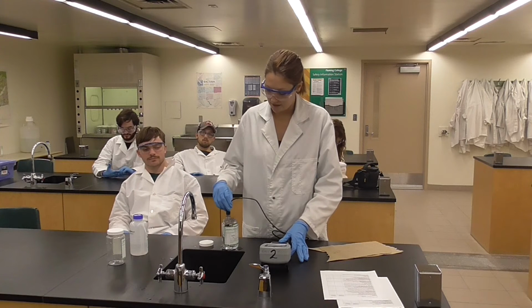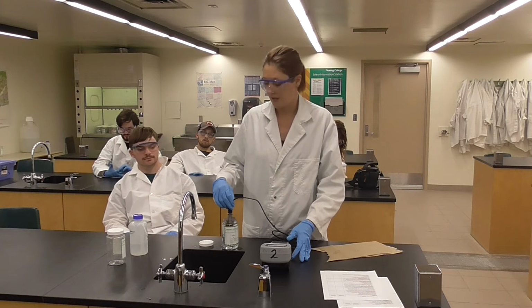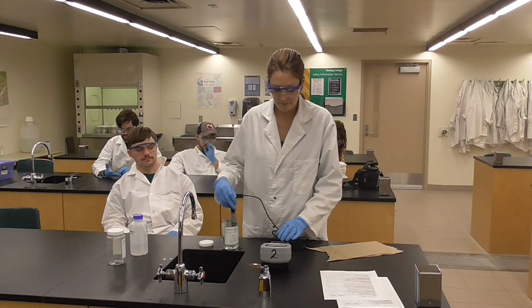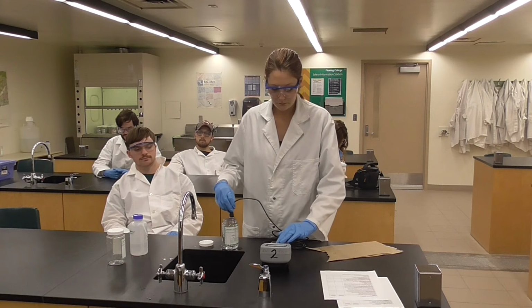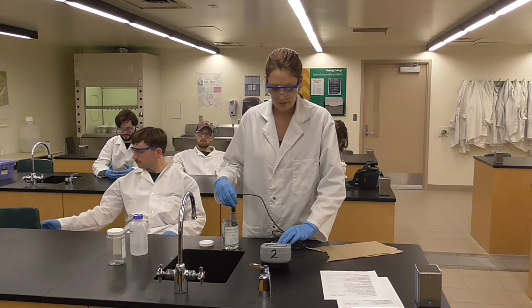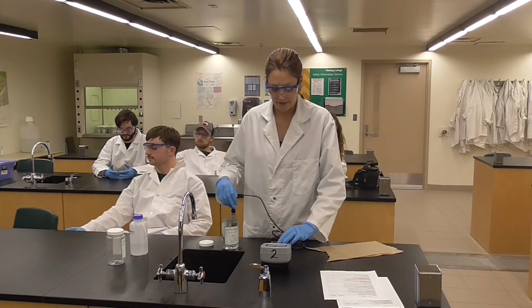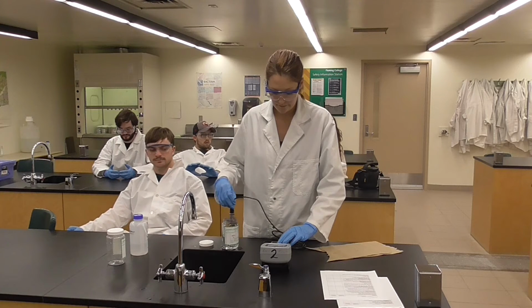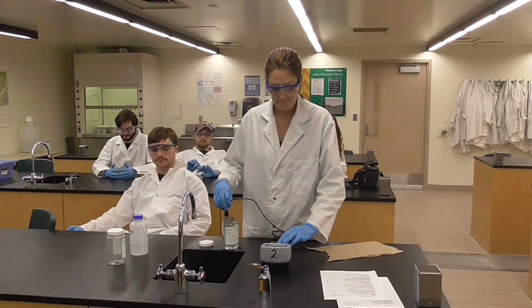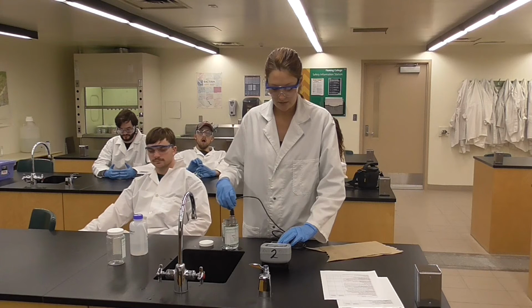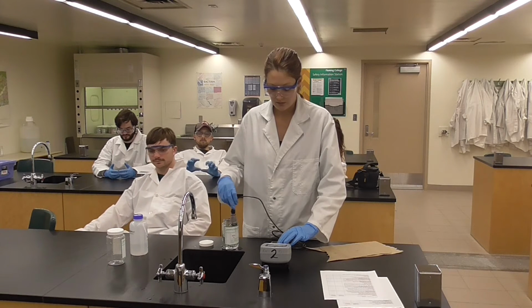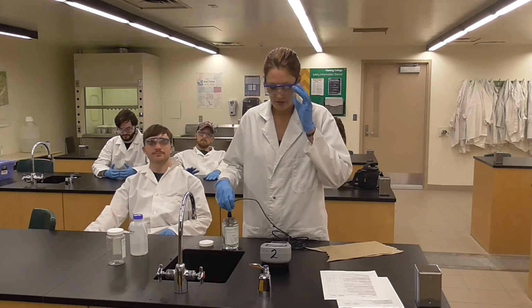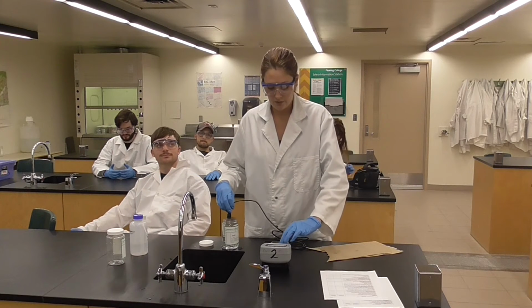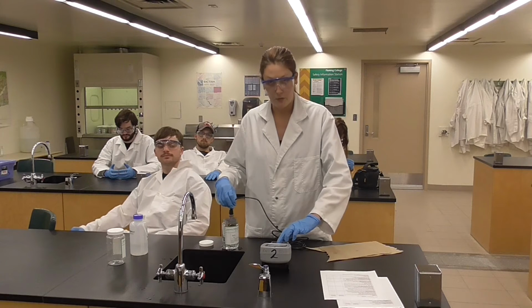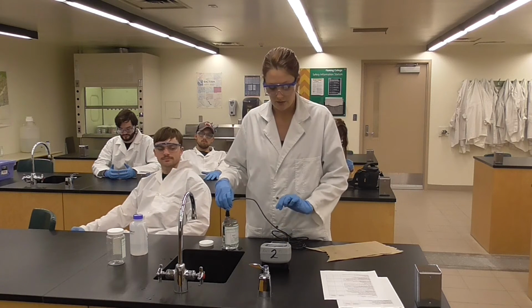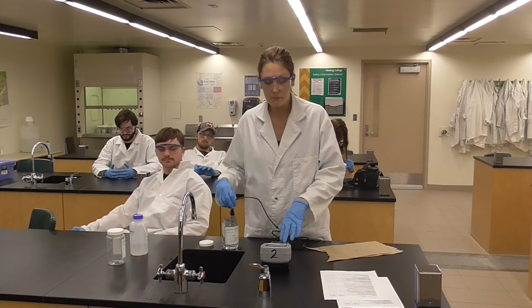Still all over the place, and it needs to just keep moving so it doesn't use up the oxygen in any one particular spot of the water sample. So the numbers are still moving quite a bit on the screen here, so I'm just going to keep going for a bit. Okay. So now to enter this machine into the calibration mode, you're going to need to press both the up and down button at the same time. So the screen displays cal.